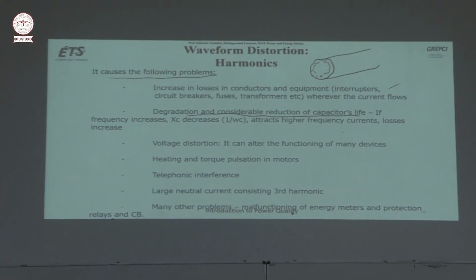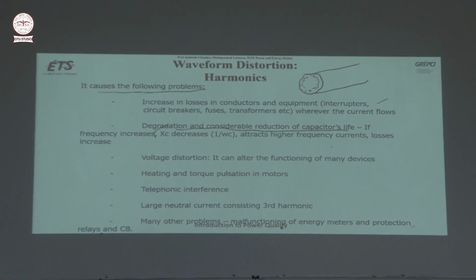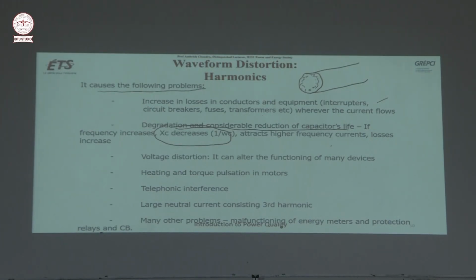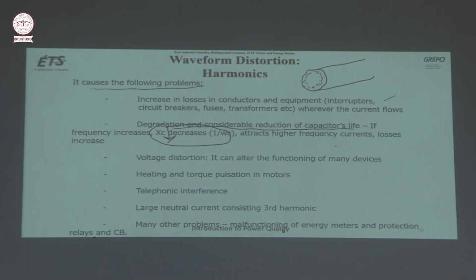Another problem is degradation and considerable reduction of capacitor's life, because of capacitive reactance, you know, 1 upon omega c. If frequency increases, then Xc will decrease and it will attract the higher frequency currents. So more higher frequency current will be attracted by your capacitor. Like I was telling you in the example, a neighbor's load was overloading the capacitor of another customer who did not have the non-linear load. The harmonic currents generated by one customer were attracted to the other capacitor nearby, overloading and heating it, and it may decrease the life expectancy.